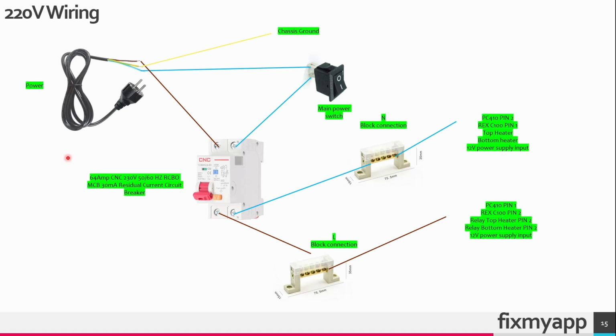Here you can see the wiring. This is the main power cord. The yellow line will go to the chassis ground. The blue neutral line will go to the main power switch. And if it's turned on, it will go through this circuit breaker. From the circuit breaker, it will go to the neutral block connection. Every connection is a neutral connection. And this neutral line will go to the temperature controller. It will go to the top heaters, the bottom heaters, and the 12-volt power supply.